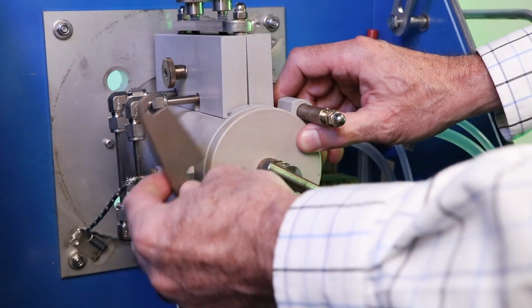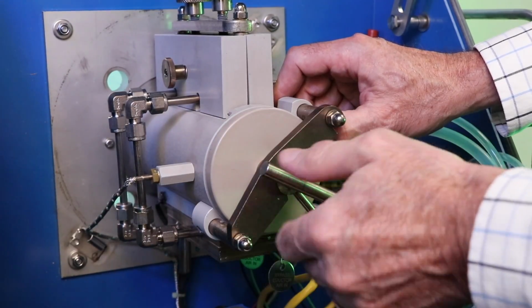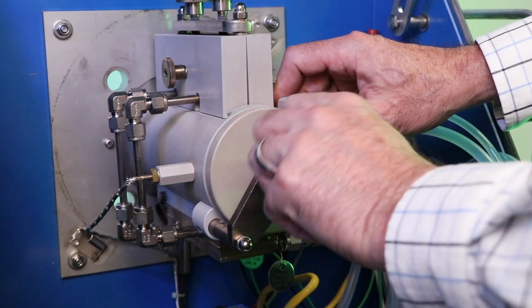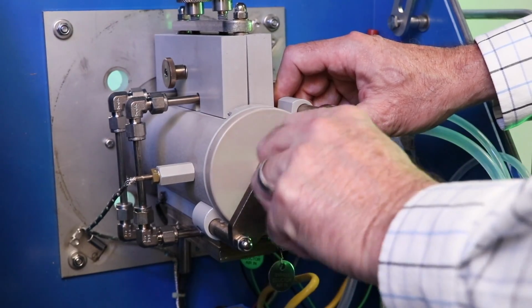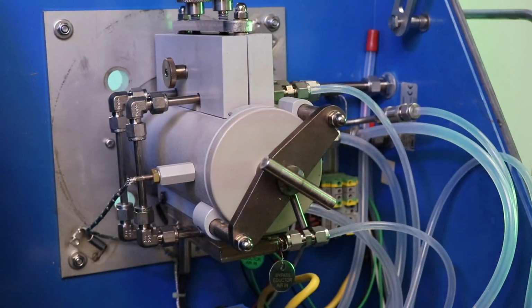Reinstall the housing in reverse order and secure the filter lid. Be sure that the knurled screw and T-handle are only finger tight when reinstalled. Apply anti-seize compound to all threaded components to prevent galling.